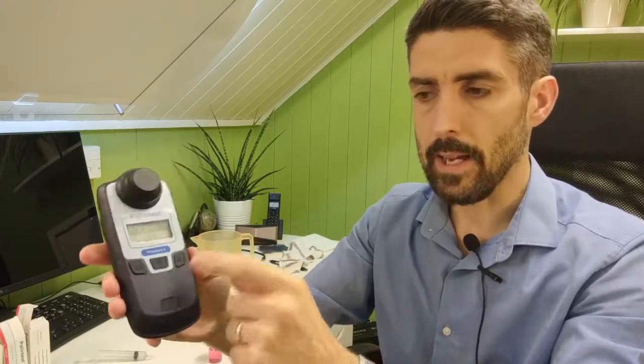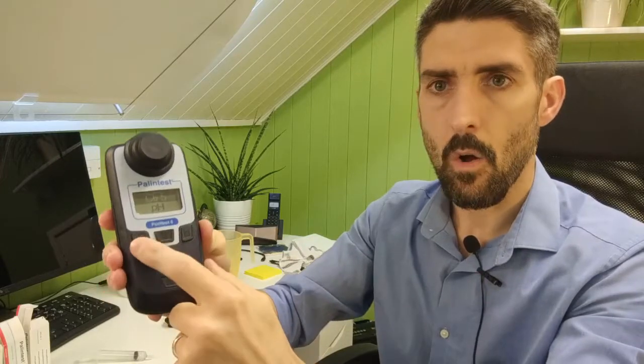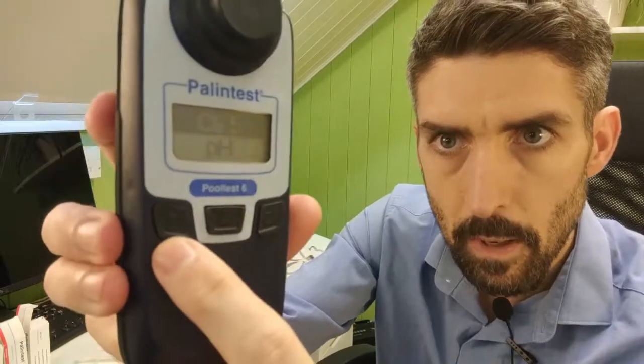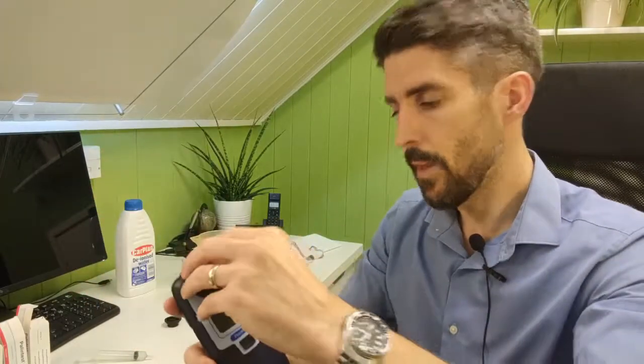But once you've got the blank in, you press the button on the left hand side. Now again, I don't know if you can see, but the buttons are slightly different. That one's a test tube with blank and the other one is a test tube that is shaded in. So because we're doing a blank, we want to make sure we're pressing the right button. It comes up as 0.